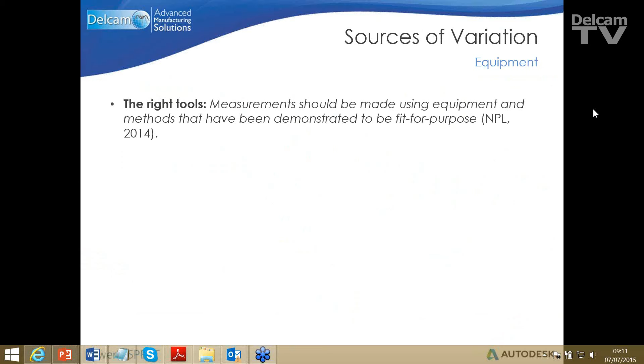Well, one of the first things we'll look at is the resolution of the equipment. What is it capable of reporting as a result? So, for example, a digital vernier caliper reads to 2 decimal places of a millimeter. So the resolution of that particular device is 0.01 of a millimeter. Obviously, without even thinking about it, we wouldn't try and measure something that had a tolerance of plus or minus 7 microns with a device that could only measure to resolutions of 10 microns. So the resolution of the equipment is quite important.